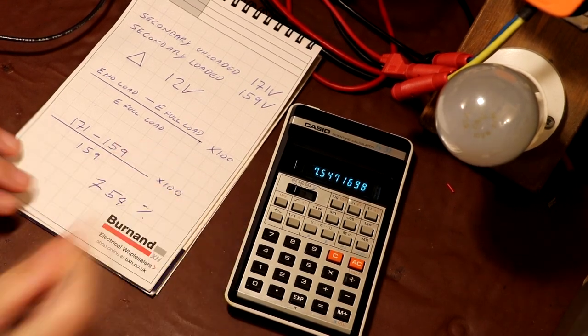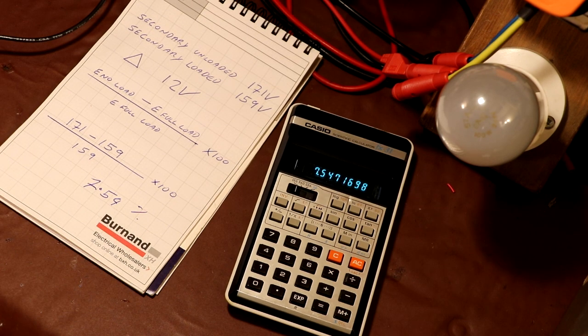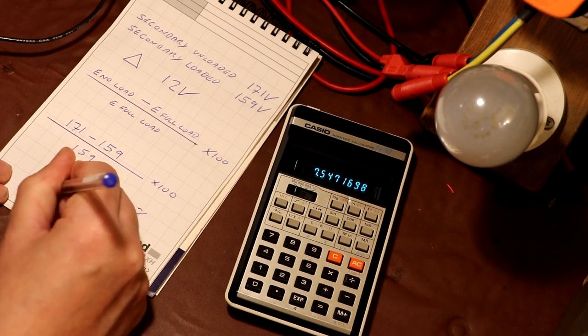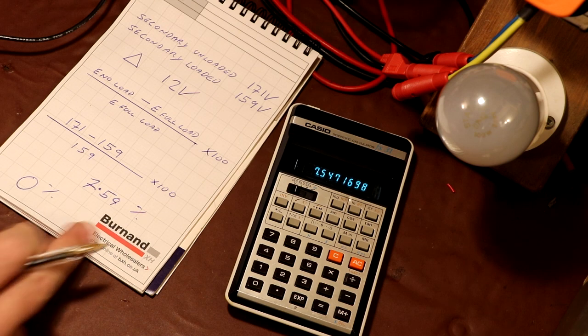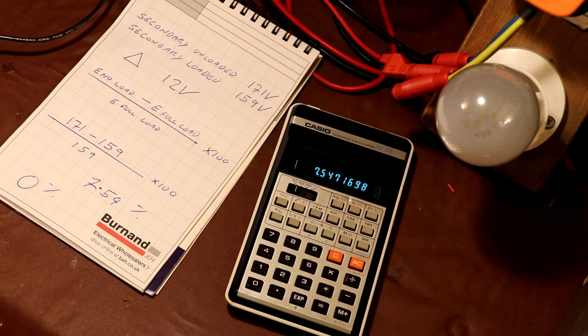7.54% regulation. Now, if such a thing existed as a perfect transformer, the actual regulation figure that we would be aiming for would be 0%. But a transformer that has 0% regulation doesn't exist. What that would mean is that you could put as much load on it as you wanted, and the terminal voltage at the secondary wouldn't drop.